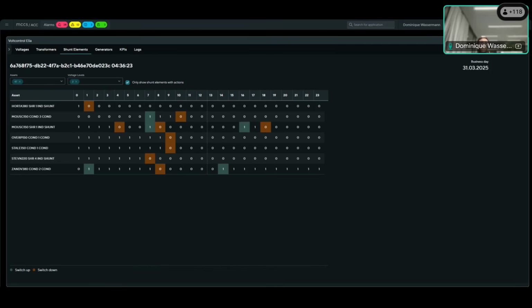Now addressing a question from the Slido briefly: how could the solution help at preventing something that happened in Spain? With Volt Control, we're not aiming at really addressing short-term oscillations that might happen, but one of the main goals of Volt Control is actually to provide the maximum amount of reactive power which is free at any given time. So what that allows us to do is essentially to, at each moment in time, have as much reactive power as we need, or which could be beneficial for usage for voltage management.